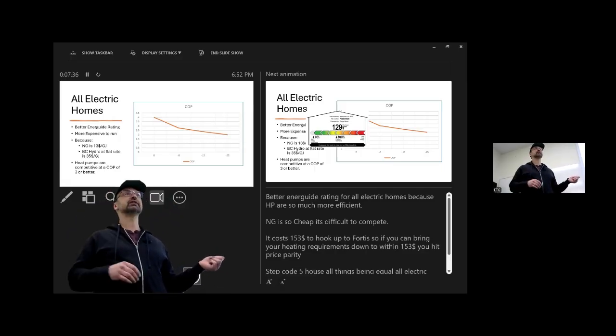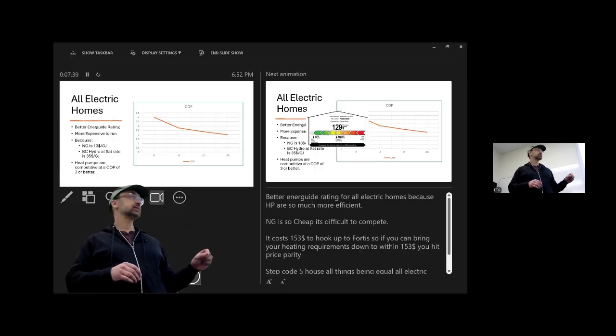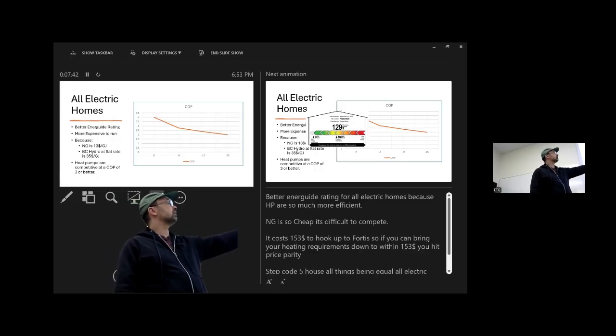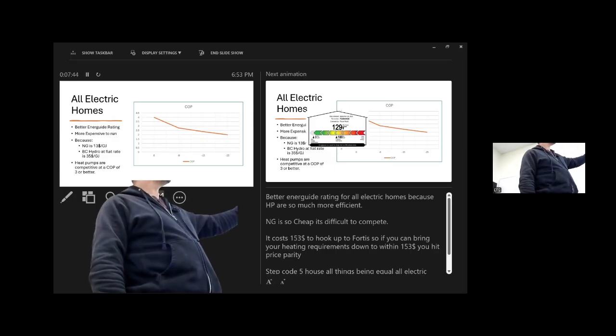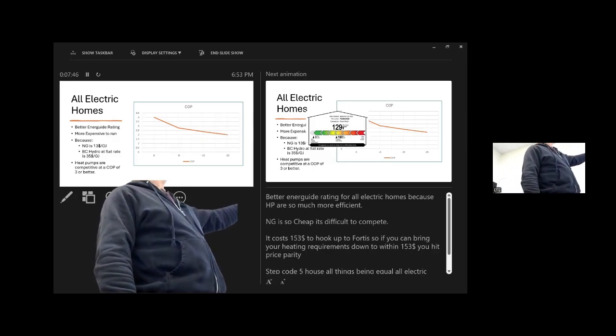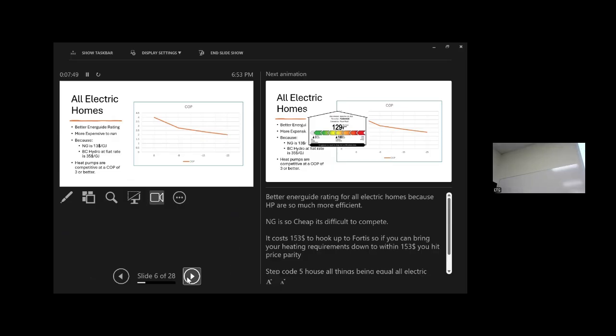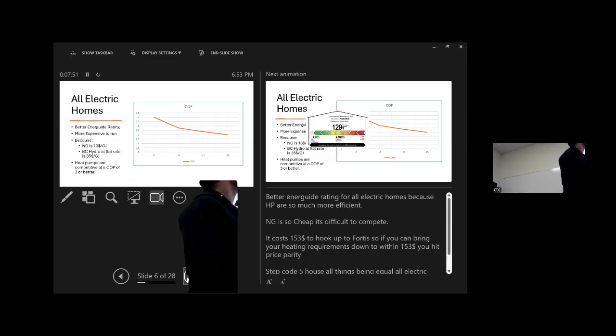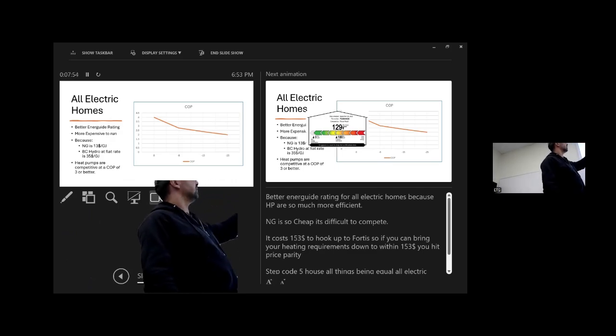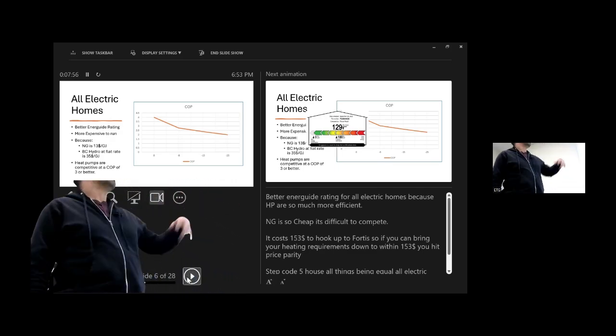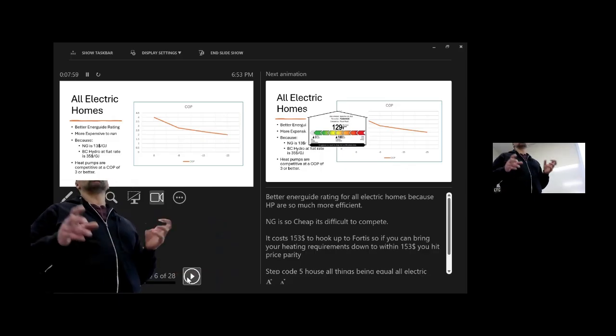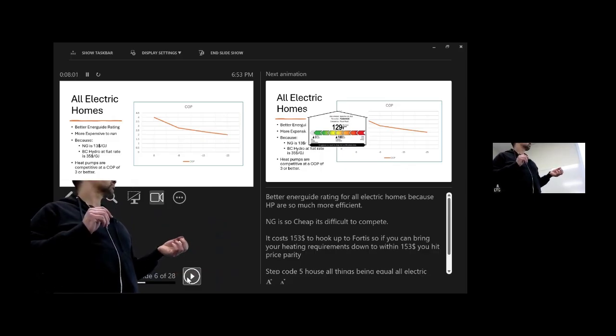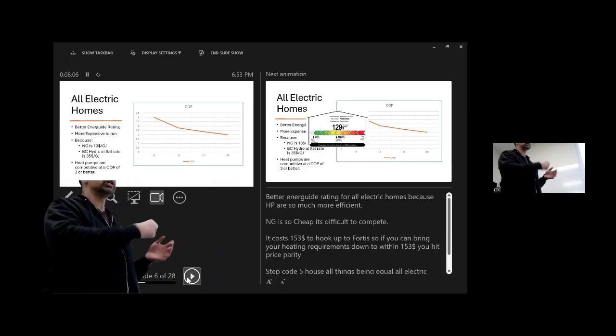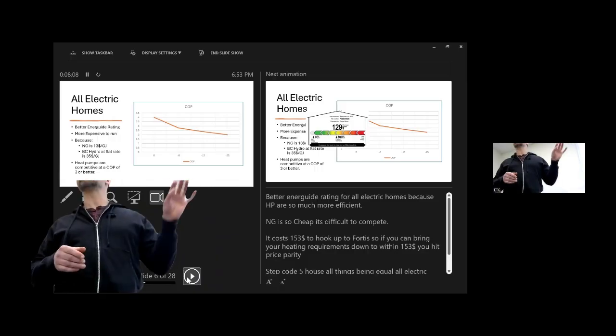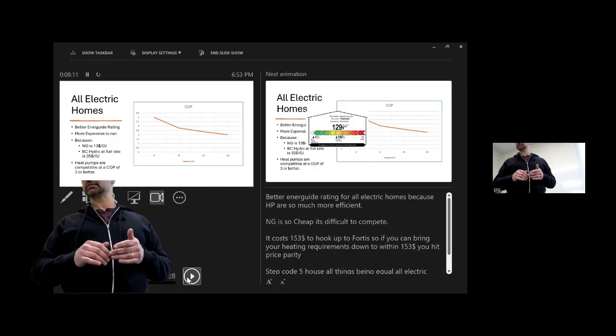So you need to get 3 units of energy out of 1 unit of electricity - this is an example of a COP for a good heat pump. This is degrees Celsius on the bottom, and COP on the other axis. You can see it goes below 3 at around -6 or so. So the heat pump is cheaper to run than a natural gas furnace up until about -4 or -5.